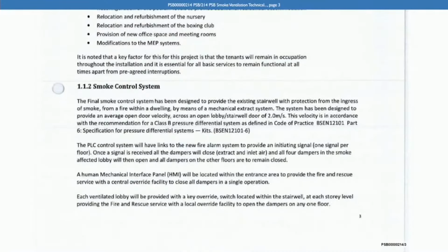I see. So I think to answer my question in a brief way, your understanding was that the system was intended not only to protect the stair, but also to provide some protection to the lobby itself. Is that correct? Yes. Yeah. Now, if we read on within section 1.1.2, in the remainder of that first paragraph, picking up in the second line, it says the system has been designed to provide an average open door velocity across an open lobby stairwell door of 2 metres per second.